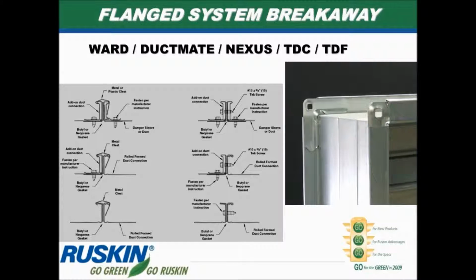There are a number of different methods to connect the ductwork to the damper sleeve using various types of flanges or even a TDC or TDF flange material where the ductwork is actually fabricated with a flange on it in the shop. And these have all been tested, and it used to be much more difficult to find the right connections, but so many of them now have been tested and approved that virtually any type of connection, whether it's ward or Ductmate on one side and TDC or Nexus on the other side, they have been tested and are approved as valid breakaway connections.